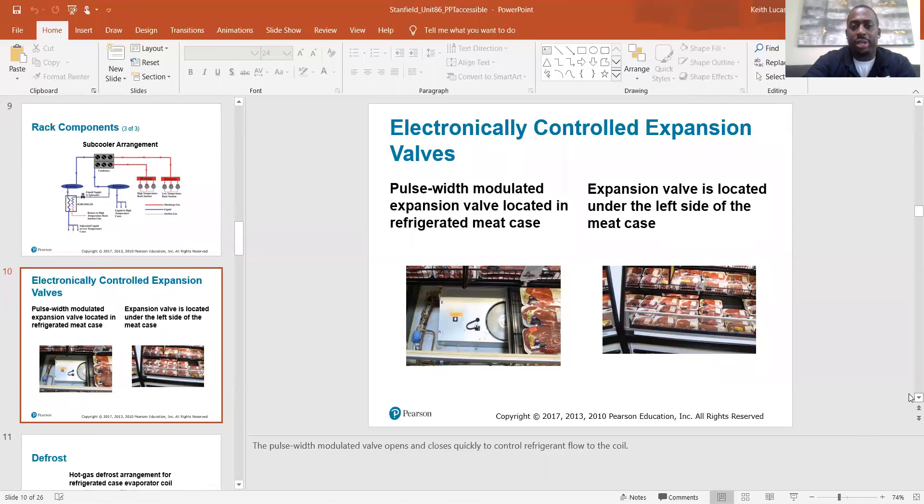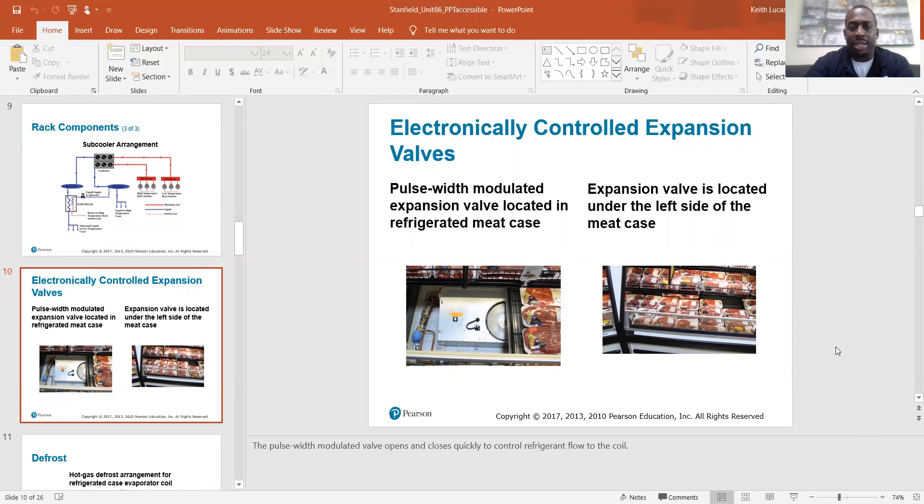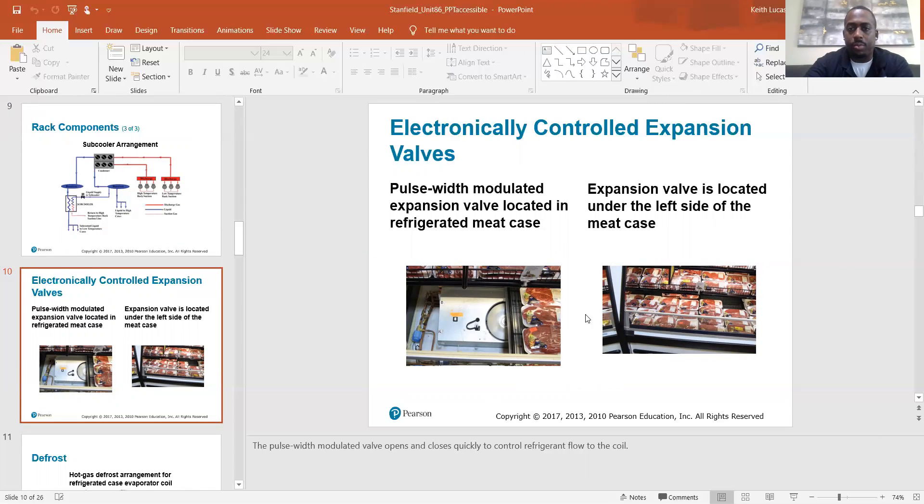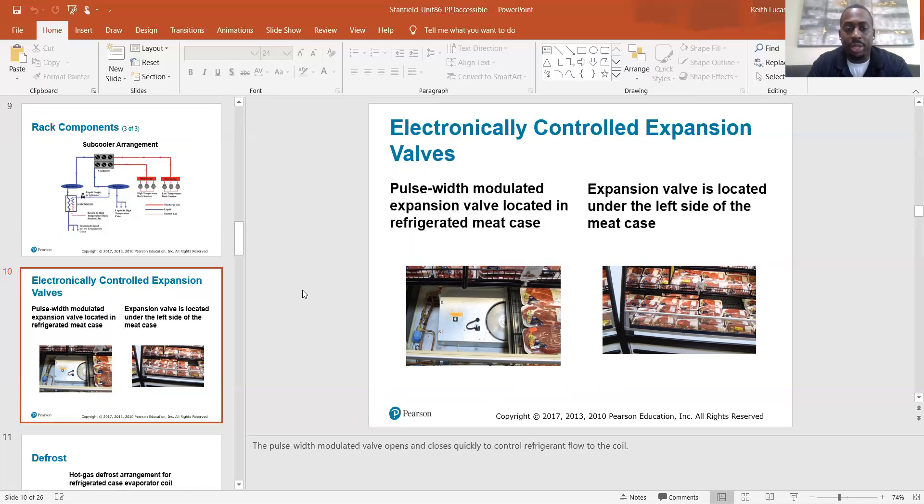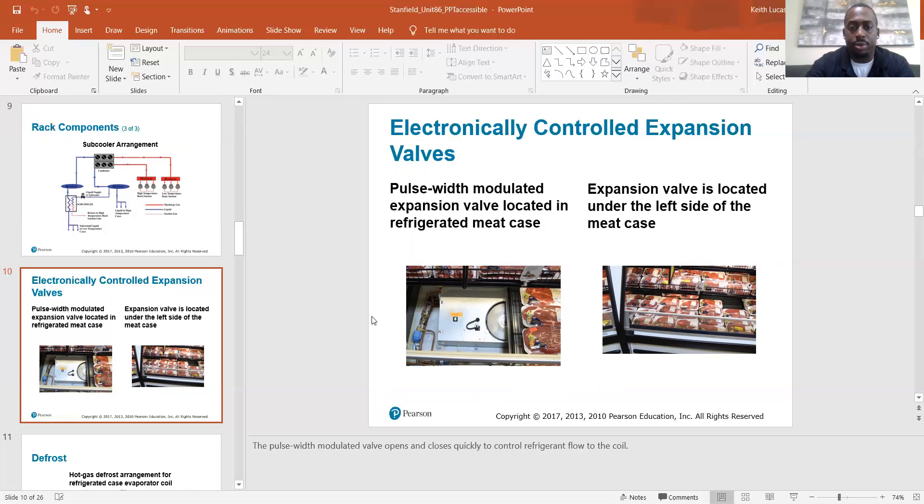Electronically controlled expansion valves. Pulse-width modulated expansion valve located in the refrigerated meat case, which is right over here. Expansion valve is located under the left side of the meat case. So they got it shown on this graphic here. So the pulse-width modulated valve opens and closes quickly to control refrigerant flow to the coil.